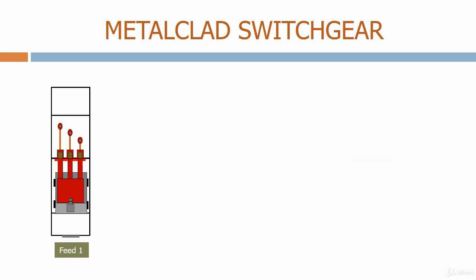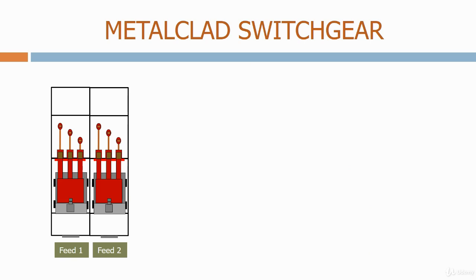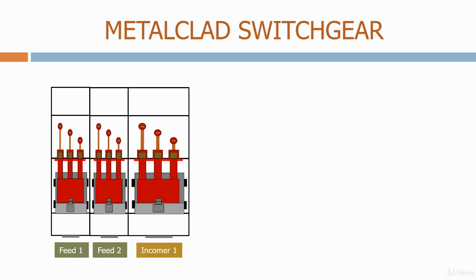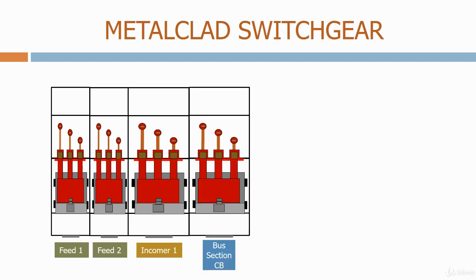Firstly we have feeder 1, feeder 2 and incomer 1. We've now completed the first bus bar. For the bus section circuit breaker we need to do something slightly different. Because both bus bars 1 and 2 are at the same height, we need to bring the bus bars down through the circuit breaker and back up again. To achieve this, in addition to the bus section circuit breaker chamber, we need to provide another chamber called the bus section riser. Let's look at the bus section circuit in more detail.